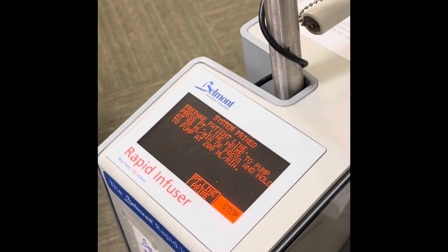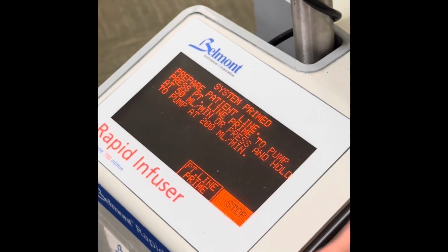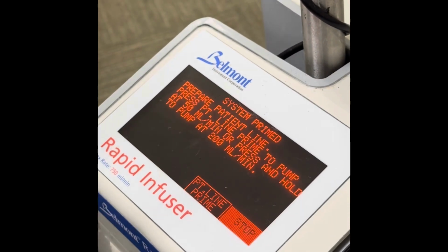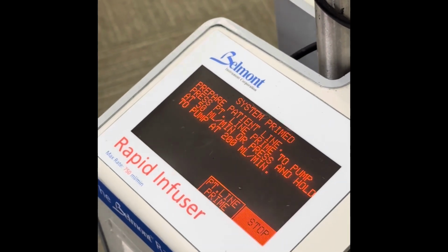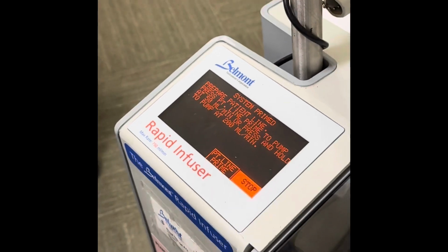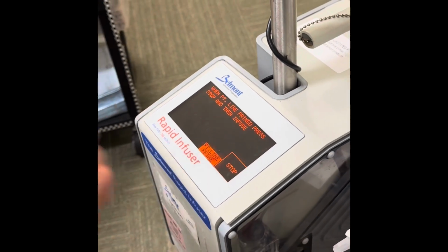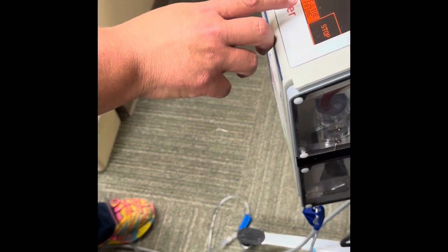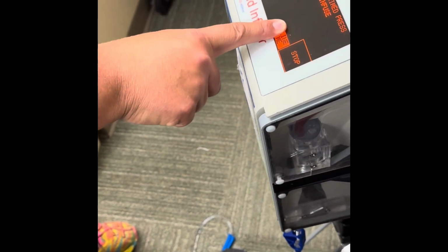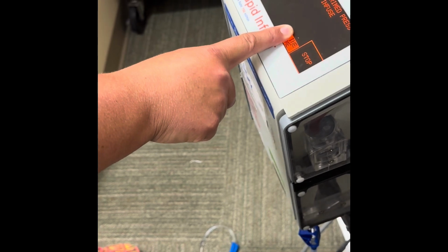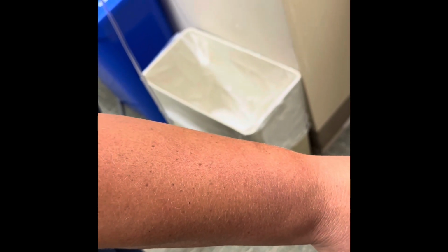It's now telling me that we have primed the tubing that is located in the machine, and we are at a point where we can start priming the patient line. So we can tap patient line and it's going to slowly prime. If I want that to go faster, I can push and hold prime my patient line and it will go much faster. It's very important that we get the air out of this machine.